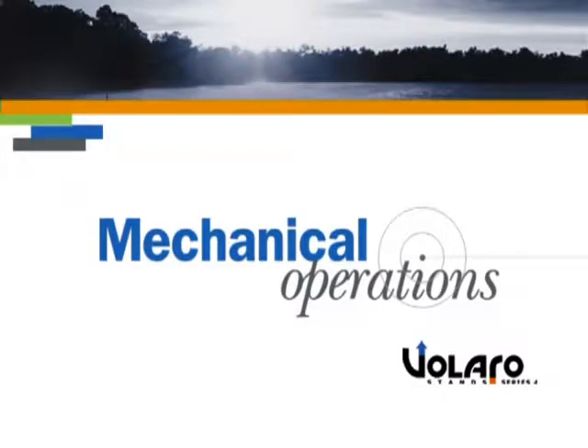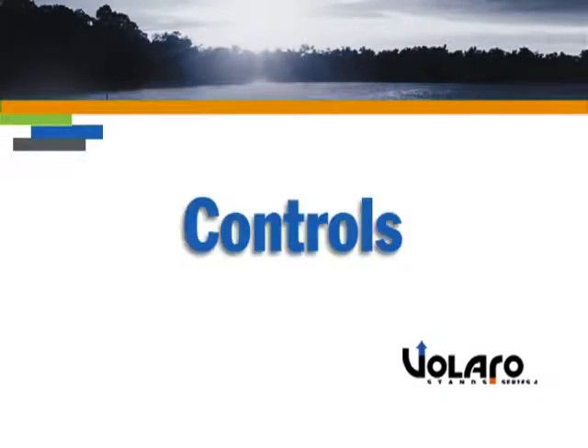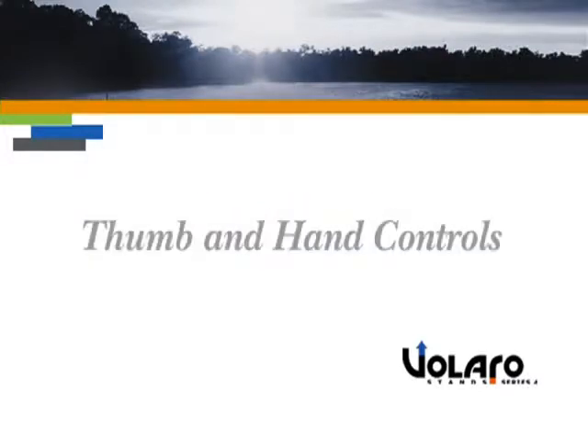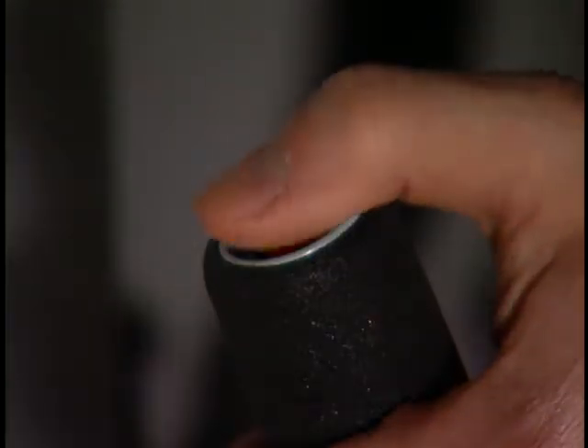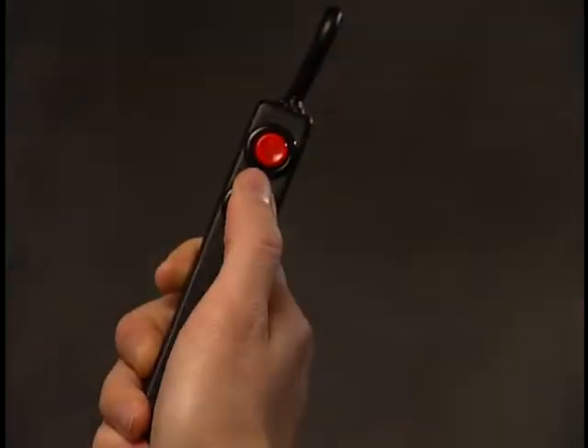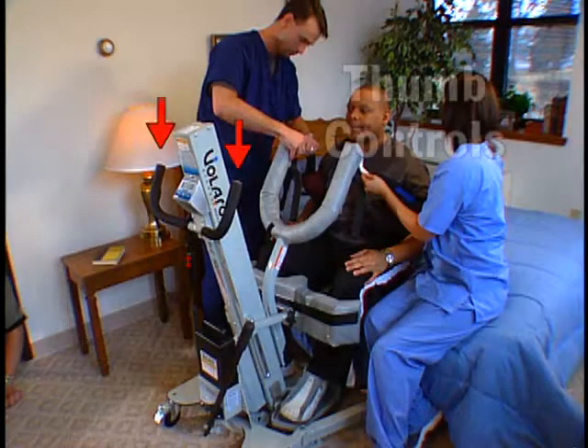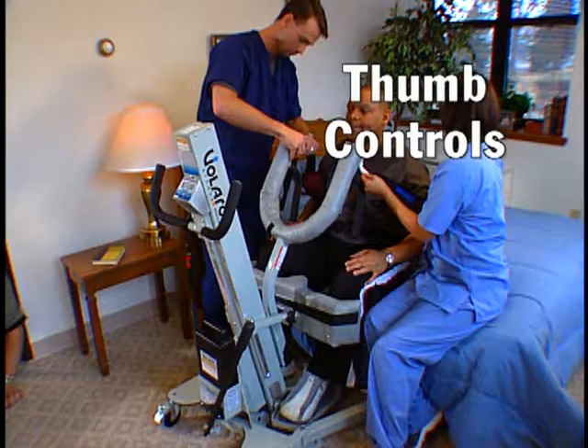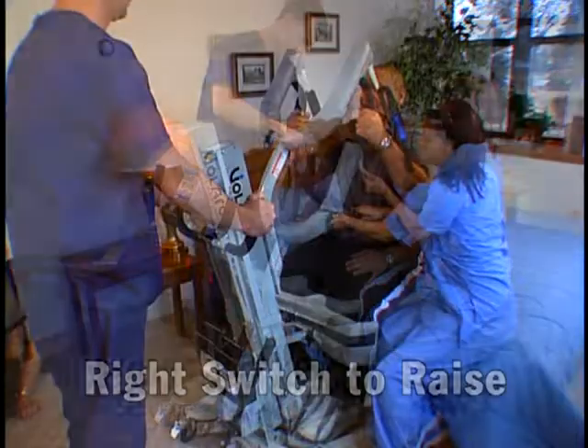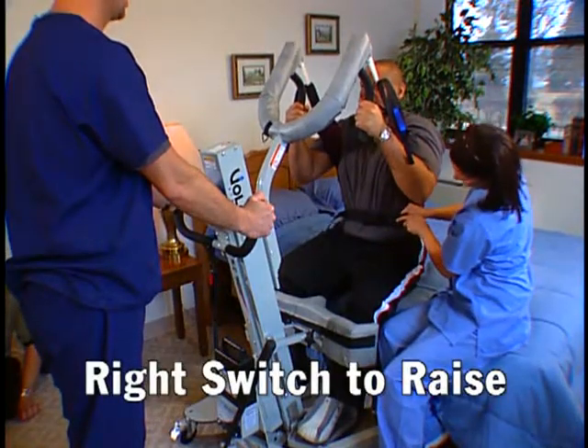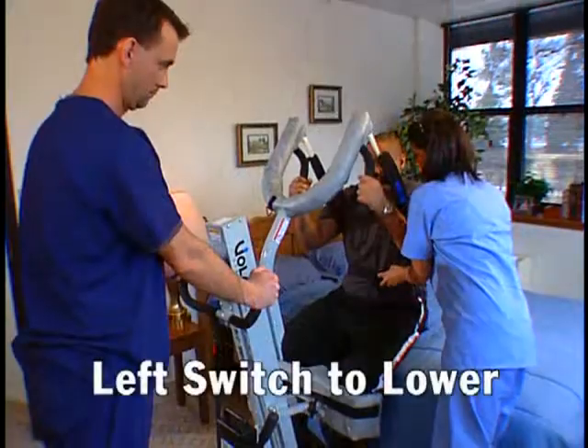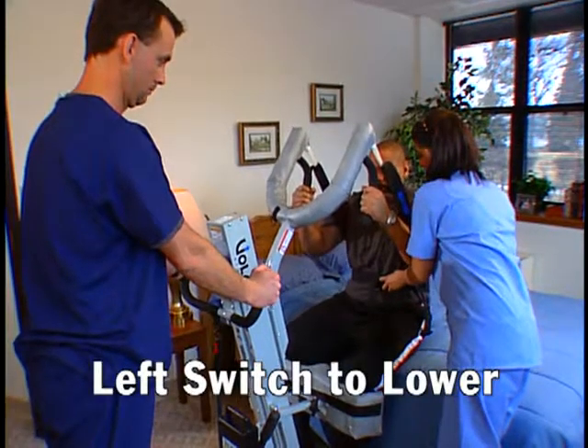Mechanical operation. Series 4 controls. Thumb controls and hand controls. The Volaro Series 4 can be operated using either the built-in thumb switches or the hand control. The thumb switches are located in the tips of the handles, allowing the caregiver to use proper ergonomics while operating the lift. Depress and hold the right switch to raise the lift arm. Depress and hold the left switch to lower the lift arm.